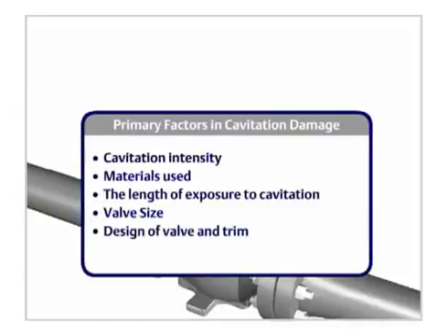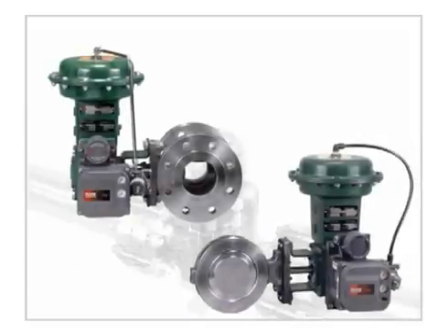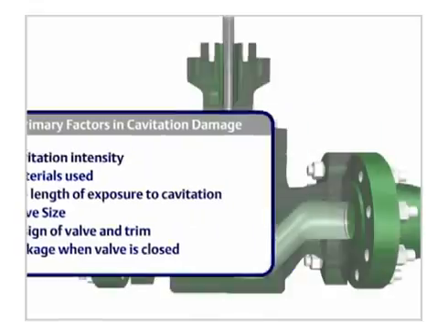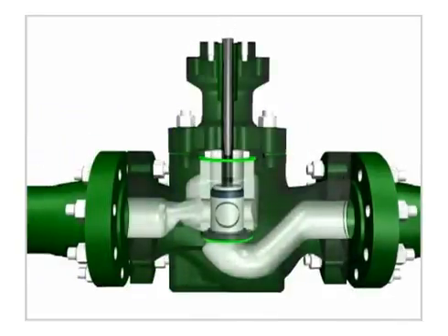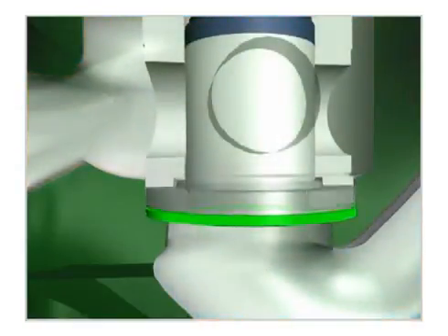The design of the valve and trim in the area of cavitation. High recovery ball and butterfly valves are more susceptible to cavitation damage. If there is leakage occurring when a valve is closed, fluid leakage moves fluid from a high pressure area to a low pressure area, which results in cavitation and potential damage.